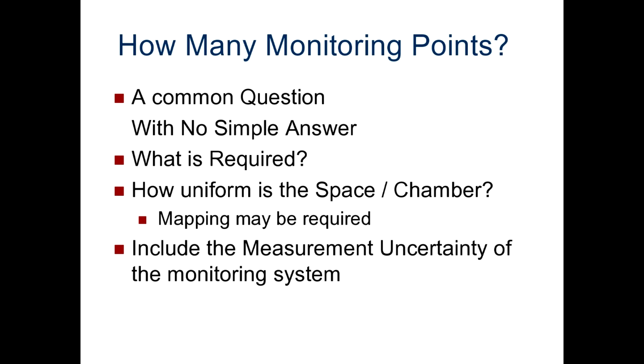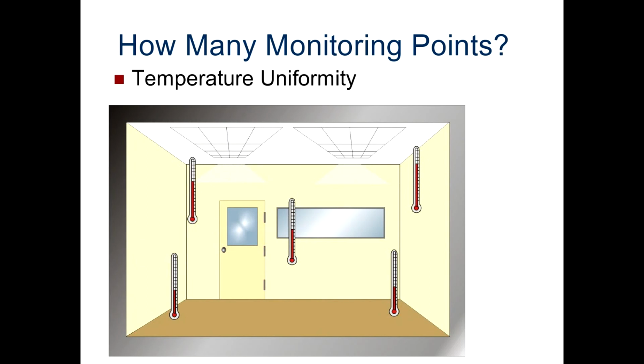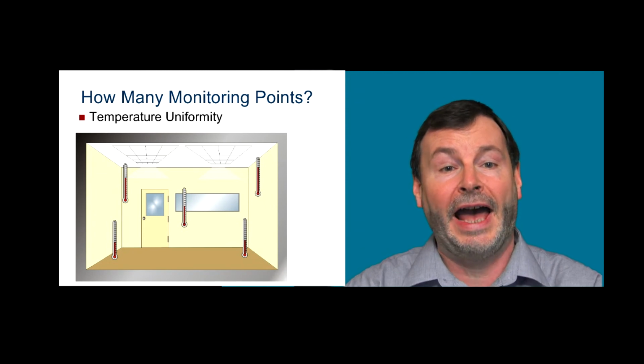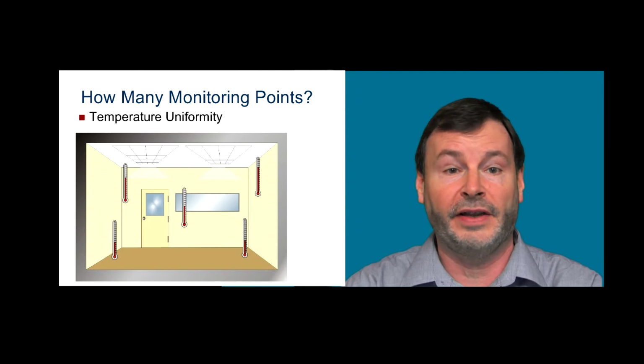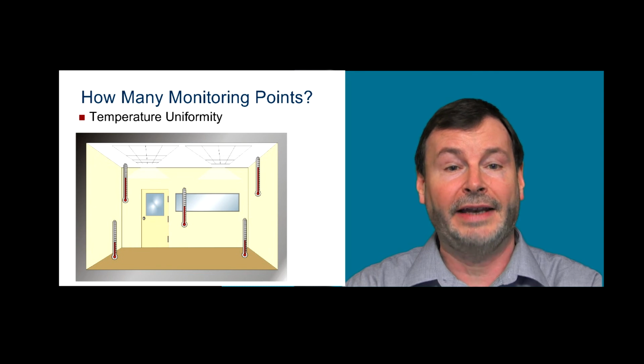And it's also important to note that you should include the measurement uncertainty or accuracy of the monitoring system whenever you are monitoring a space. Now in this case, we'll look at a room, and temperature uniformity will greatly influence the humidity uniformity. If we were to map this room out and find a 2 degrees C variation in temperature, that alone would yield a 6% humidity gradient throughout that room. Now if we add an accuracy value for the measurement system of, let's say, 2%, we're already at 8%.